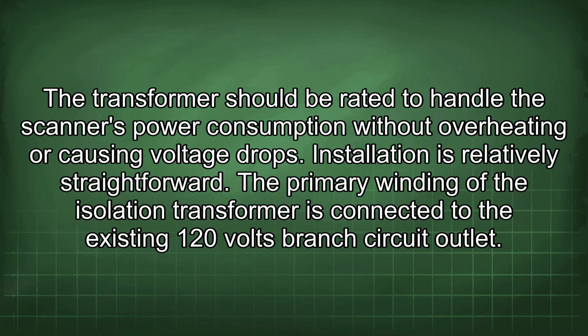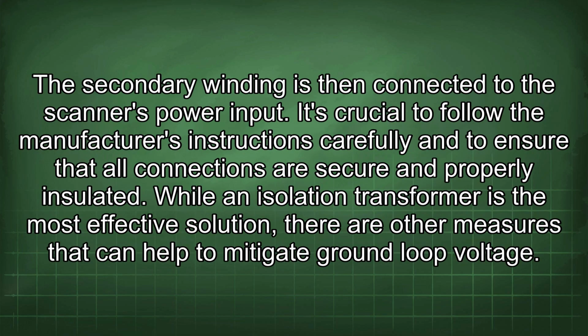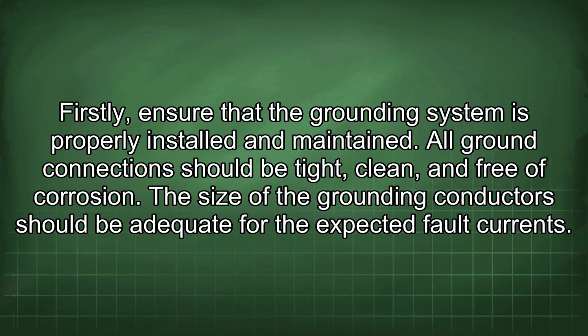Installation is relatively straightforward. The primary winding of the isolation transformer is connected to the existing 120 volts branch circuit outlet. The secondary winding is then connected to the scanner's power input. It's crucial to follow the manufacturer's instructions carefully and to ensure that all connections are secure and properly insulated. While an isolation transformer is the most effective solution, there are other measures that can help to mitigate ground loop voltage. Firstly, ensure that the grounding system is properly installed and maintained. All ground connections should be tight, clean, and free of corrosion. The size of the grounding conductors should be adequate for the expected fault currents.